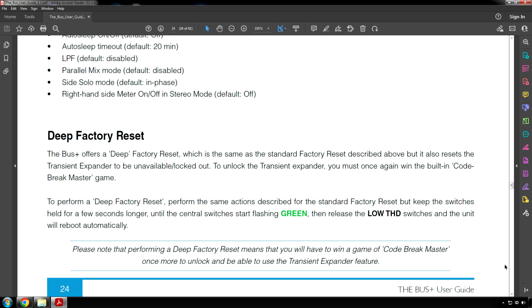Deep factory reset. The Bus Plus offers a deep factory reset, which is the same as the standard factory reset described above, but it also resets the transient expander to be unavailable or locked out. To unlock the transient expander, you must once again win the built-in Code Breakmaster game. To perform a deep factory reset, perform the same actions described for the standard factory reset, but keep the switches held for a few seconds longer until the central switches start flashing green. Then release the low THD switches and the unit will reboot automatically.